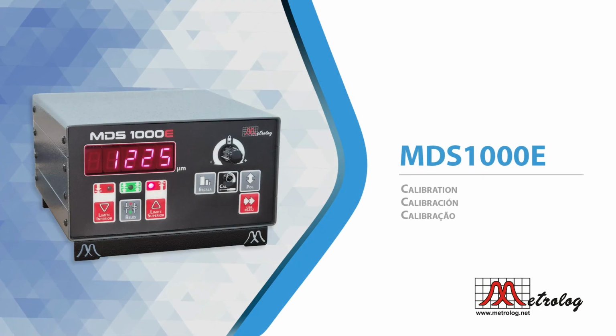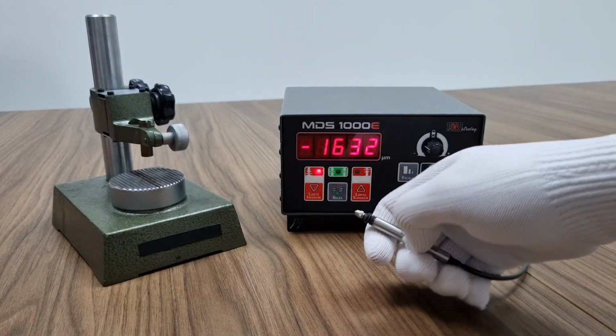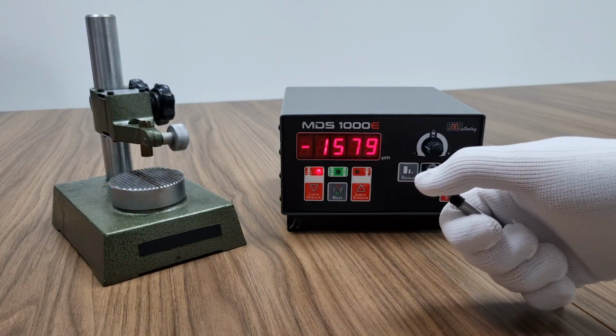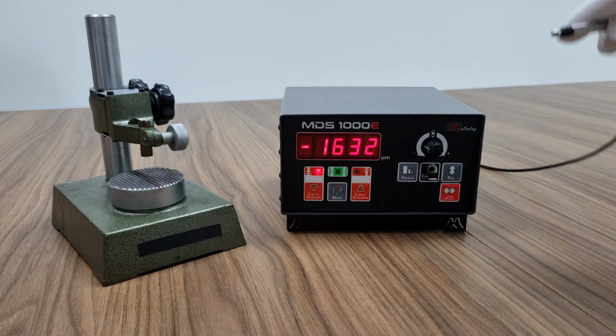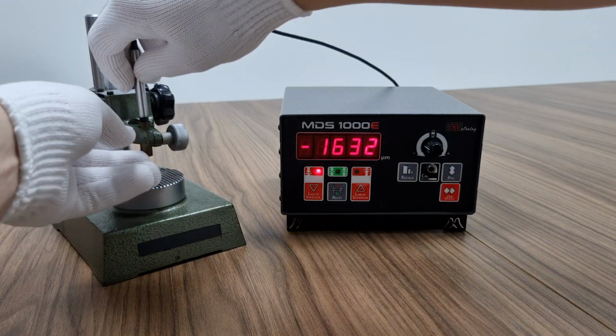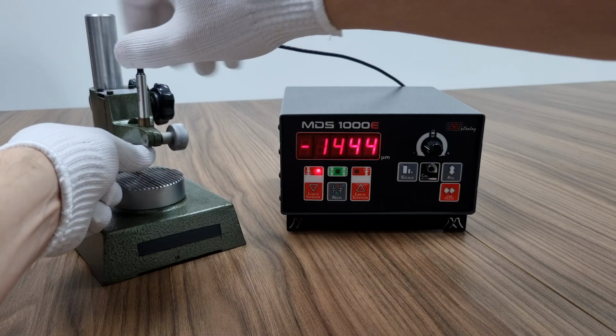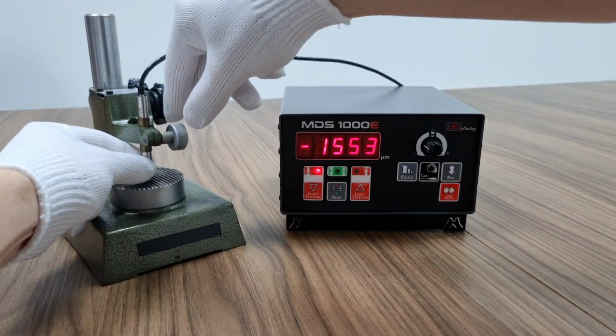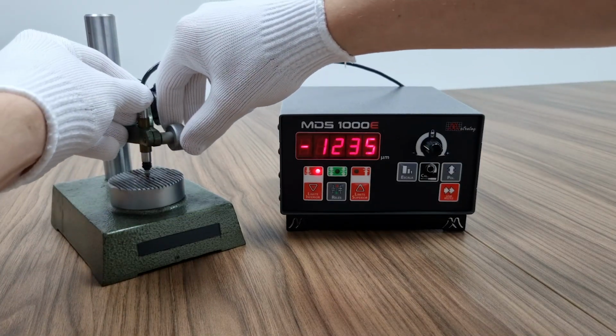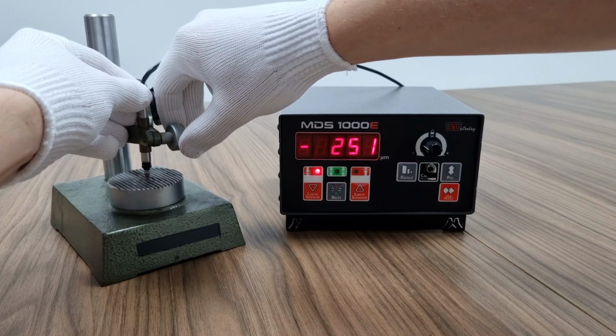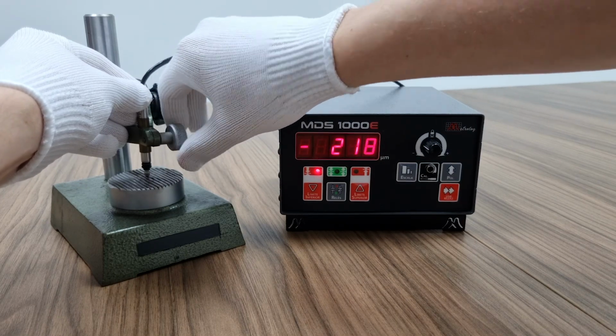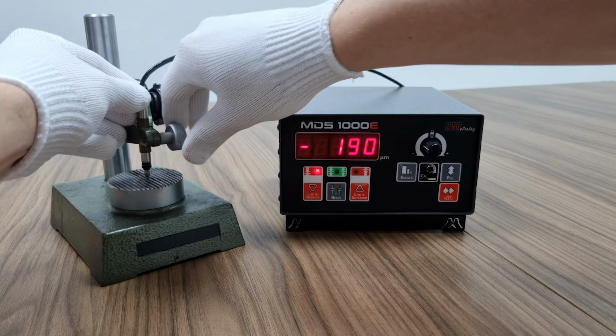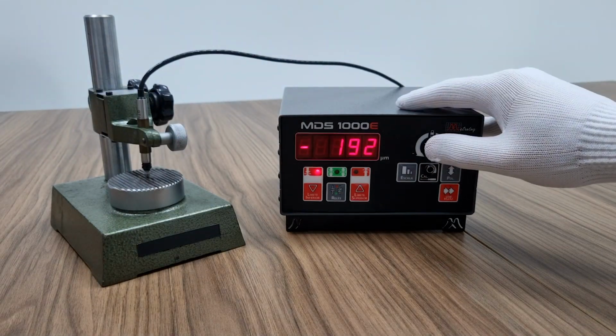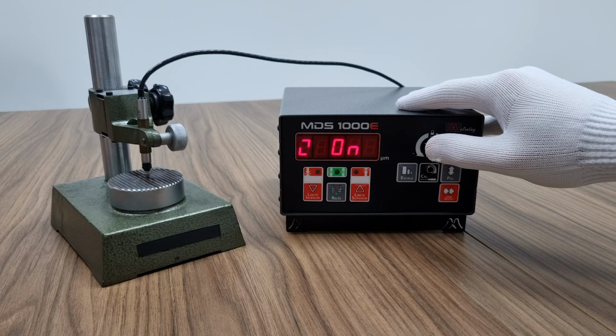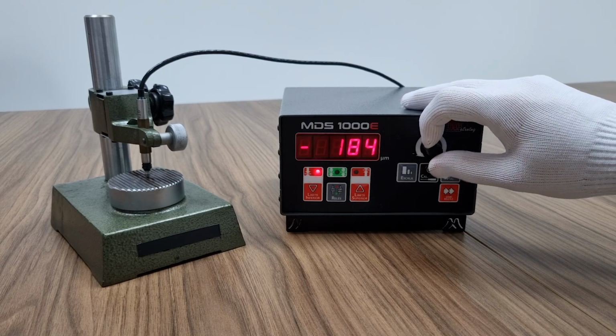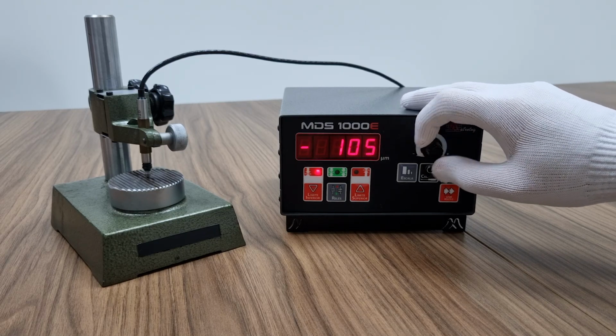Calibration. The calibration process on the MDS1000E is simple. The sensor must be fixed to a universal measurement base or micrometer drum, so that a known displacement can be applied to the sensor. In this example, the sensor is fixed near its mechanical center, and this point is considered the reference zero. The fine zero adjustment is done via the adjustment knob. The adjustment function must be unlocked by pressing the knob for 2 seconds.